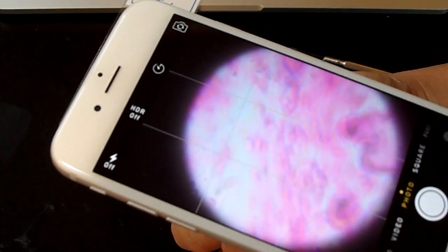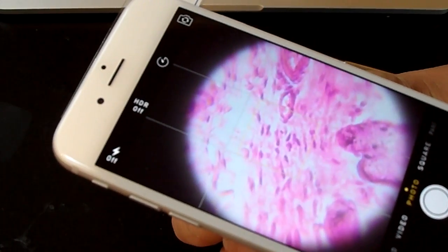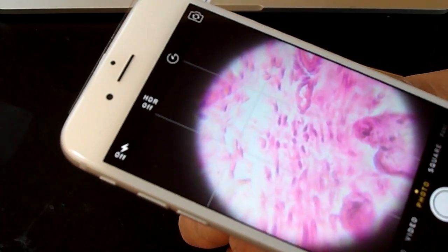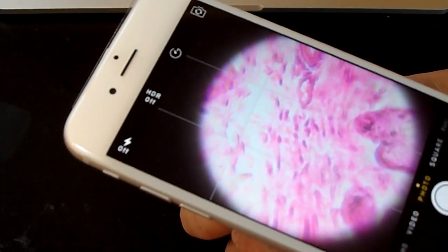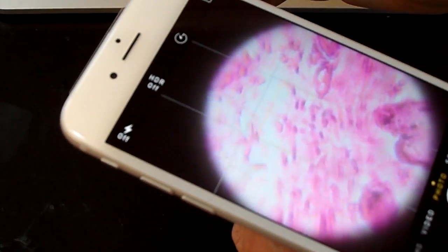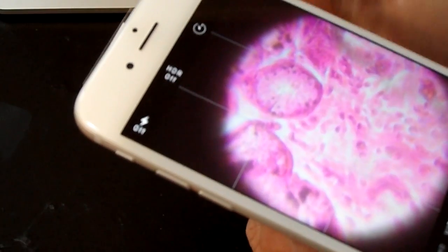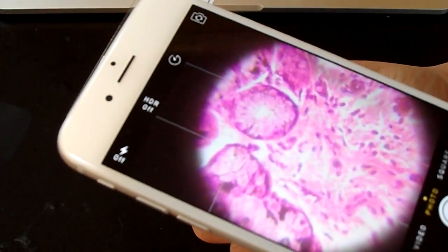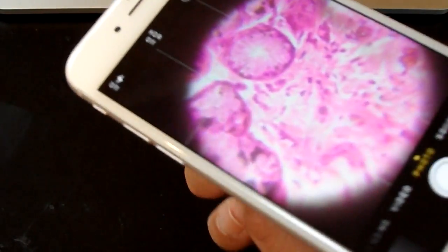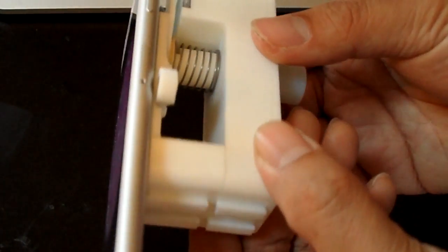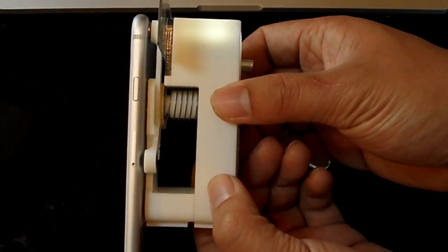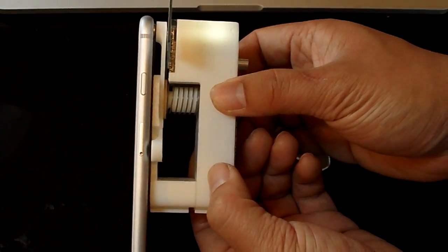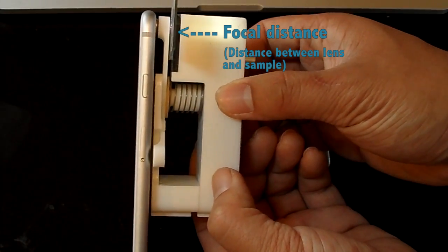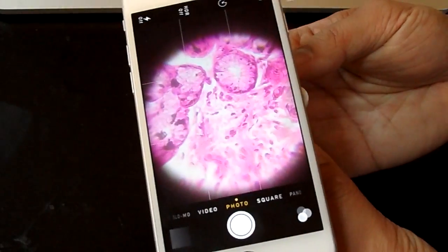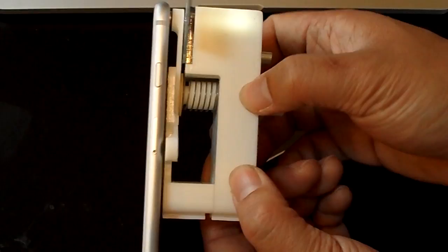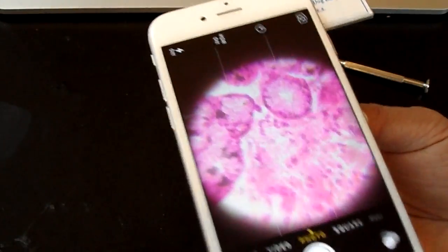And so now I'm focusing the image and inching my way closer. You can always turn back and try to focus it again, but there's a little bit of a slop, and what that means is that when you turn back, it won't turn back immediately. And basically that slop is dependent on how much you tighten the screws on the lid. And once again, I just wanted to show you how close the lens is to the sample in order to get a focused image. And as you can see, once again, it's really, really close, but the knob turns in really small increments, so you won't have too much trouble getting it there.